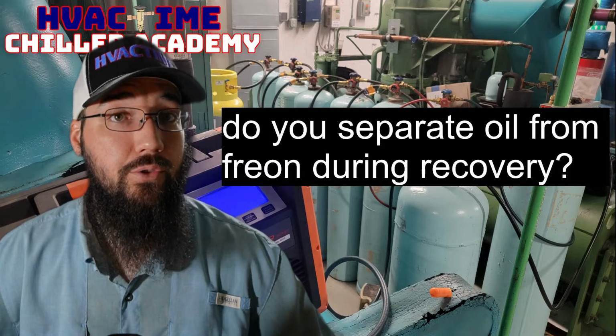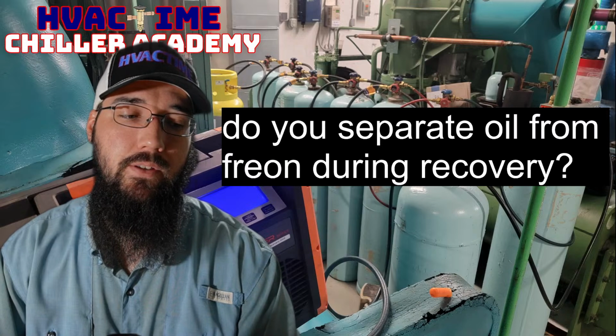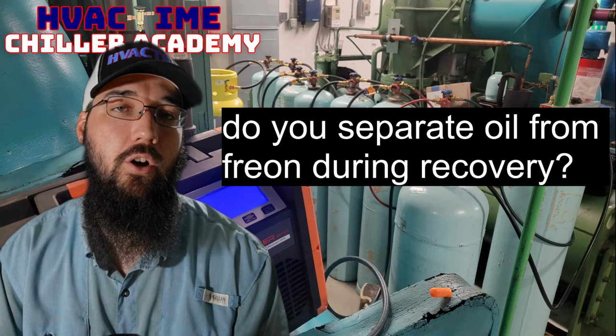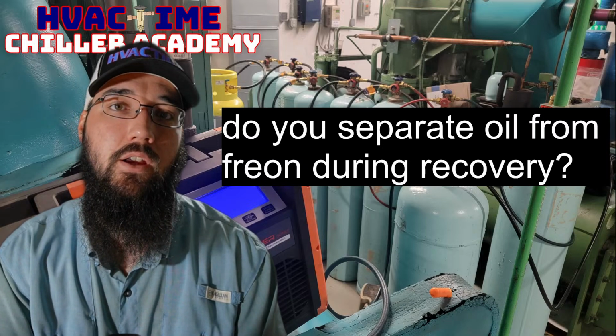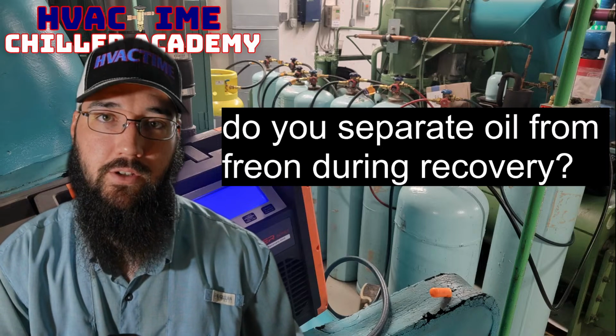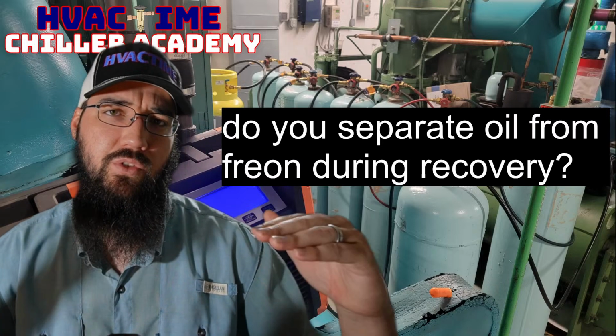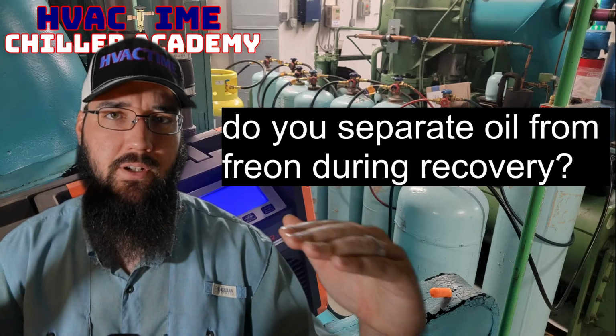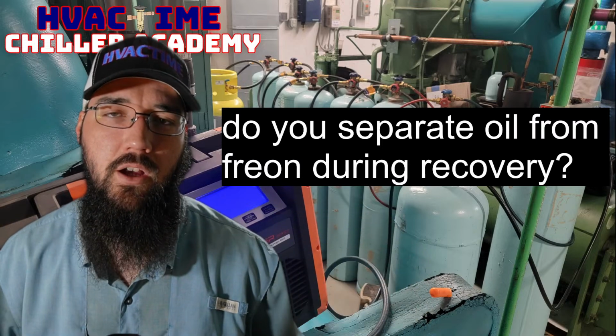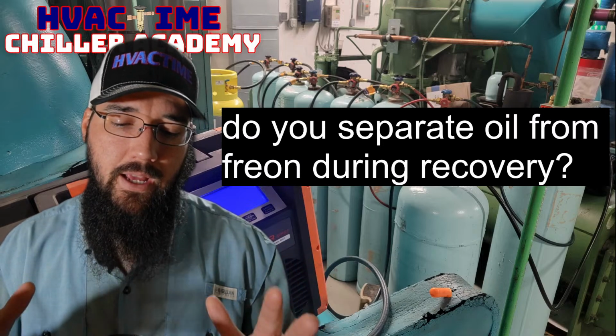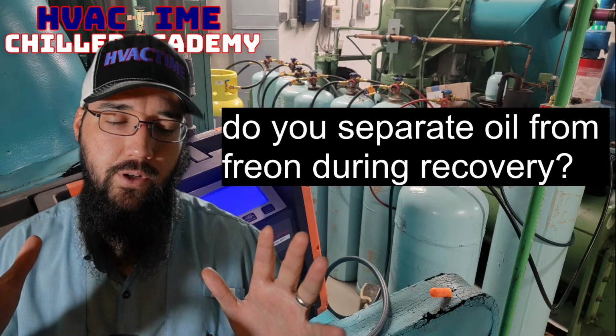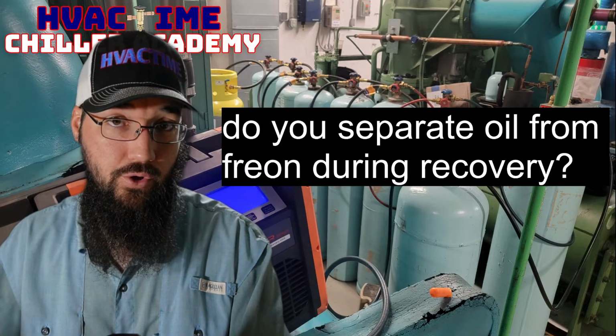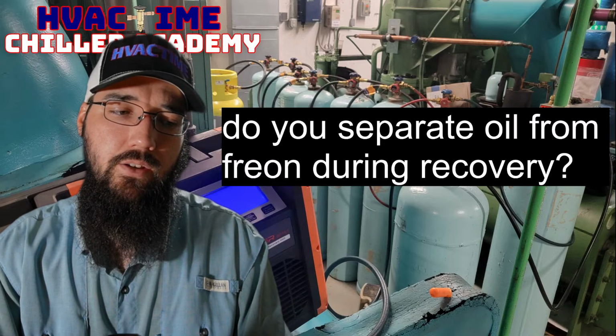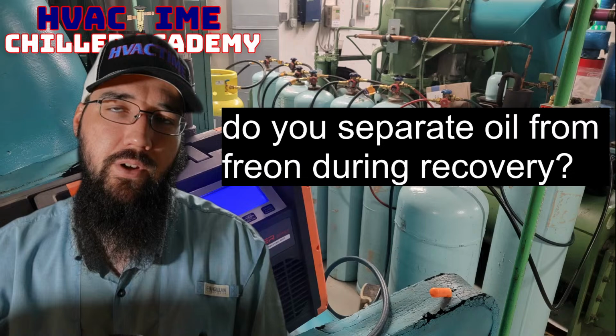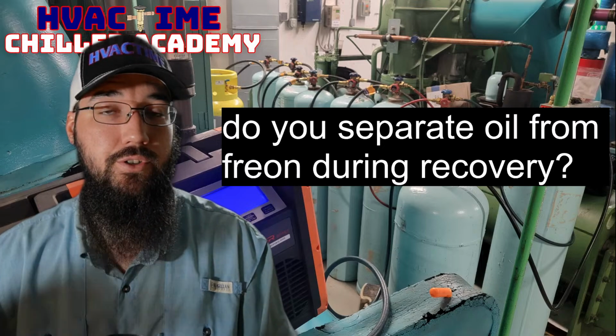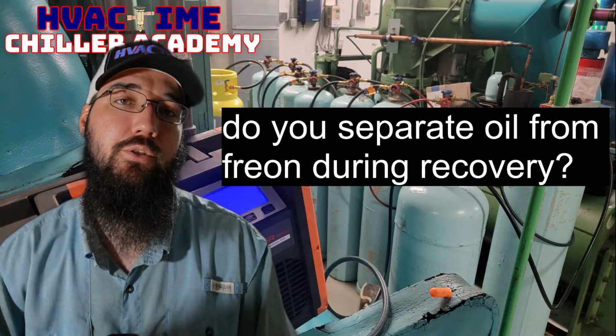You're going to go through the full recovery, and when you're done, all of that oil is going to have mixed with the refrigerant just in the process on its own, right? And that oil is going to settle at the top of the refrigerant level, so the oil is going to sit up on top of the refrigerant. Once you get ready to go back to charging that refrigerant, you have to vaporize that entire charge back into the machine. So you won't charge liquid back, you would charge vapor back.